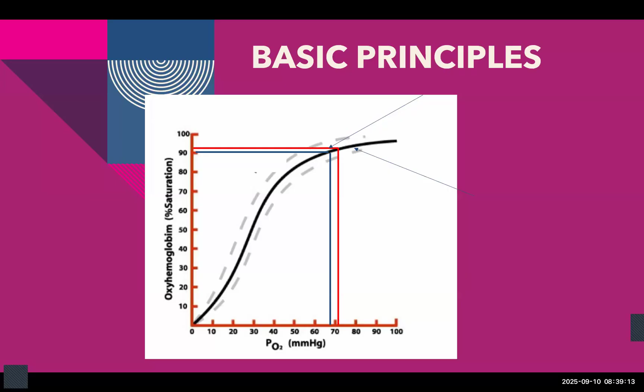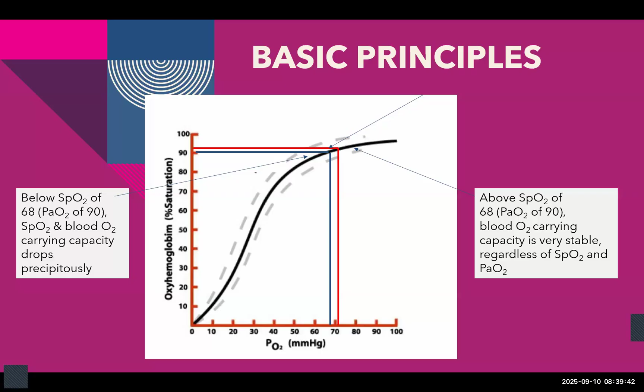Once you hit that magic number of 90, after that time, the ski slope gets really exciting. It gets very steep. And so with a small change in your PO2, your O2 saturation, and therefore your blood oxygen carrying capacity, drops very quickly. Pulse oximeters like this one all have an error range of about plus or minus 2%. So if you are aiming for an O2 sat of 92, there's a 95% chance your actual saturation is at least 90. And that's where that magic 92% comes from that you see in all the orders at CHEO.